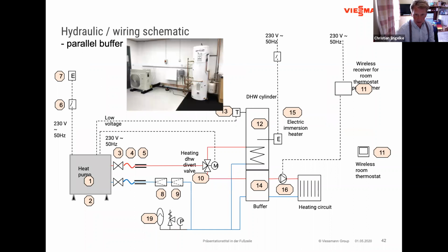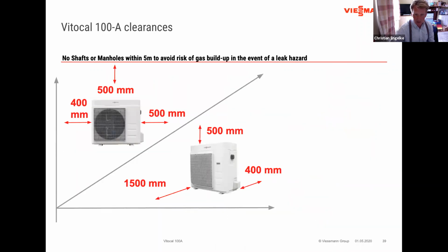Now we can cascade these machines up to 7, but that means you need 7 individual single phase cables to the unit, and then that needs to be checked with the power supply whether you have got enough. The 100 amp power supply will certainly be stretched to the limit. I think 3 phases available. The building's currently heated electrically. Yeah, so we'll have to look at other options there.